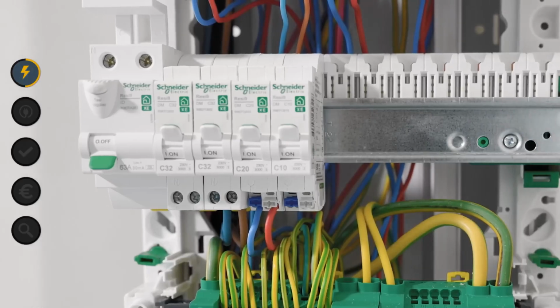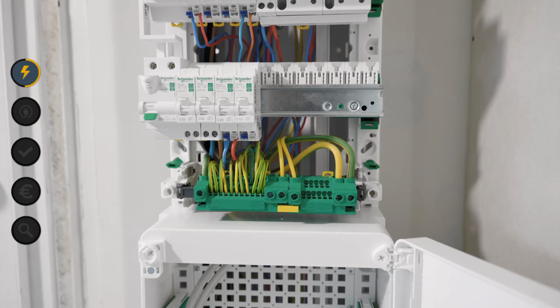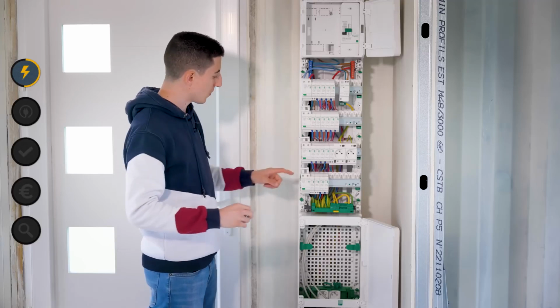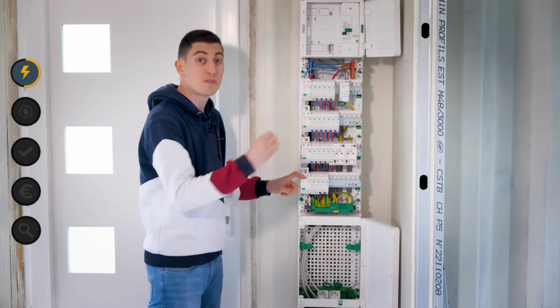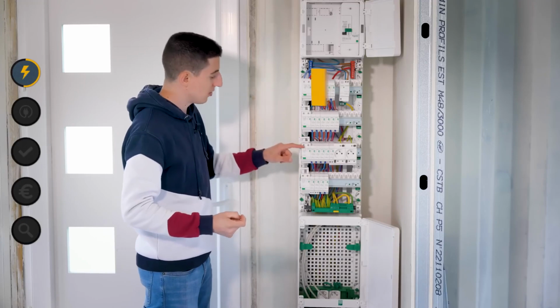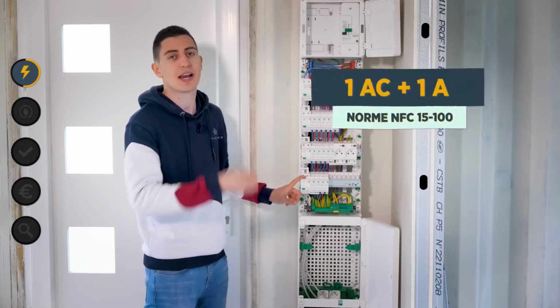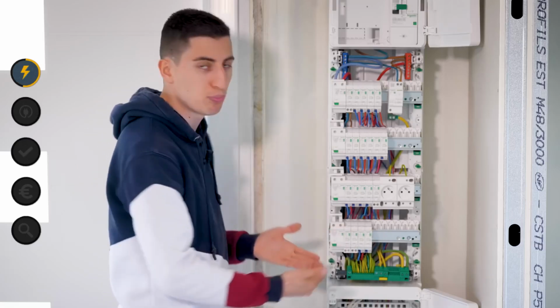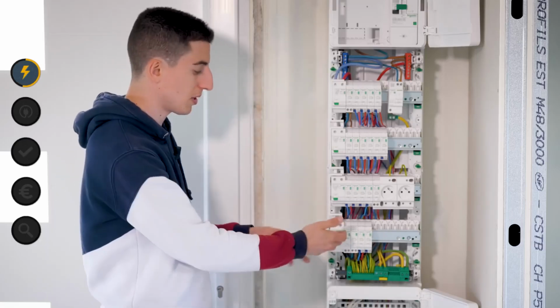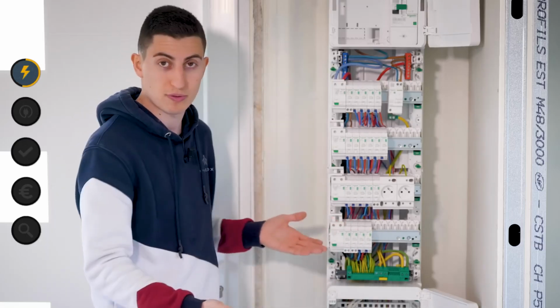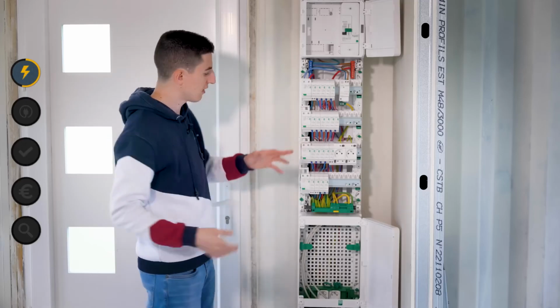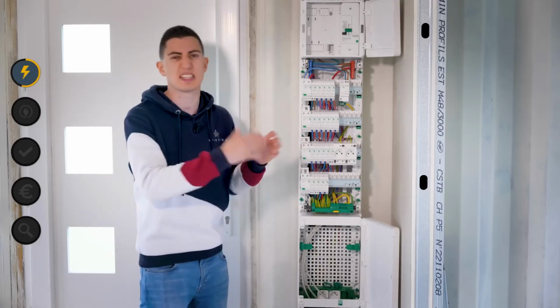You see me, I put my 3 on the right line, so normally it's good. This is all regulated in the NF C 15-100 standard. In fact, this standard indicates that on an electrical panel there must be at least one alternating current differential and one A type differential, to be able to precisely put your washing machine, your hob, all that on the right differential. So now you know which differential to choose between the alternating current or the A type.